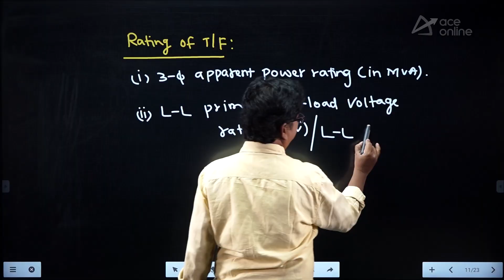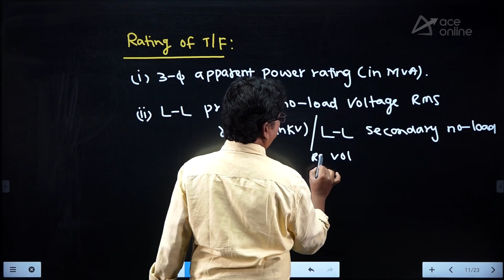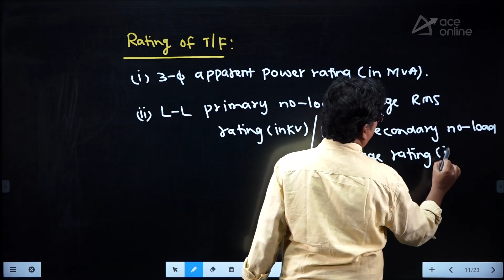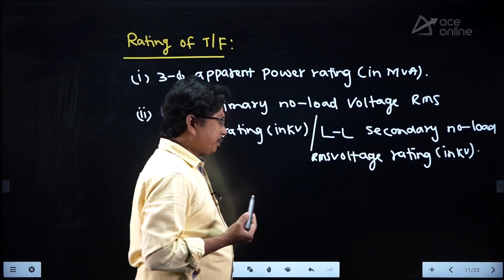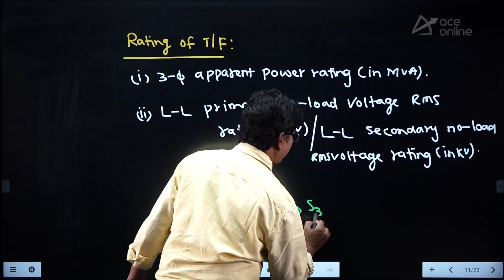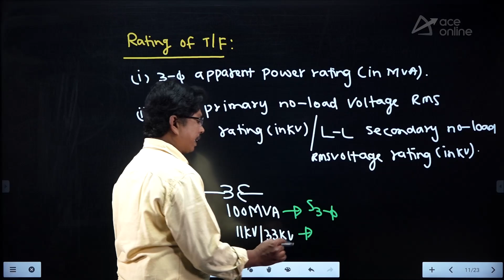Line to line, secondary no load RMS voltage rating, which should be given in kilovolts. So both primary and secondary no load voltage ratings we have to give, right? Therefore, whenever you have a transformer and you say 100 MVA, 11 kV/33 kV, then this 100 MVA will be 3-phase apparent power, and 11 kilovolts/33 kilovolts are both line to line voltages on primary and secondary. So V line primary, V line secondary.